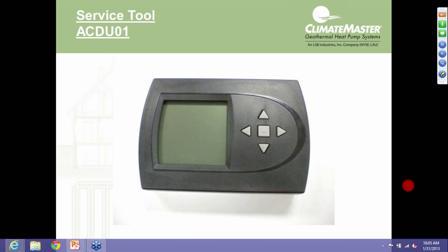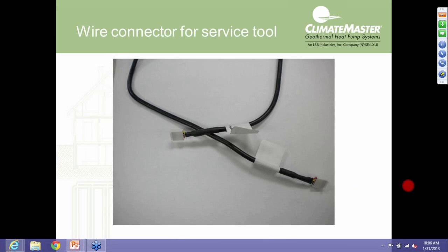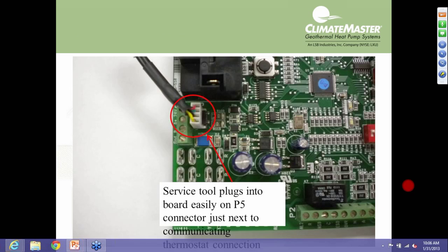But again, I highly recommend the service tool because 9 times out of 10, that thermostat is not in close proximity to the unit. You're either going up and down a flight of stairs or in and out of an attic to get to that thermostat. With the service tool, you can plug it right in front of the heat pump and go through the processes that you need to in order to commission the heat pump or look at any kind of service information. All right, so with that service tool, it comes with a wire whip with 2 Molex plugs on it. And so it makes it an easy connection to the control board. And again, you can plug it in on the fly. Plugs right into the P5 connector, which is right next to where the communicating thermostat would hardwire in.